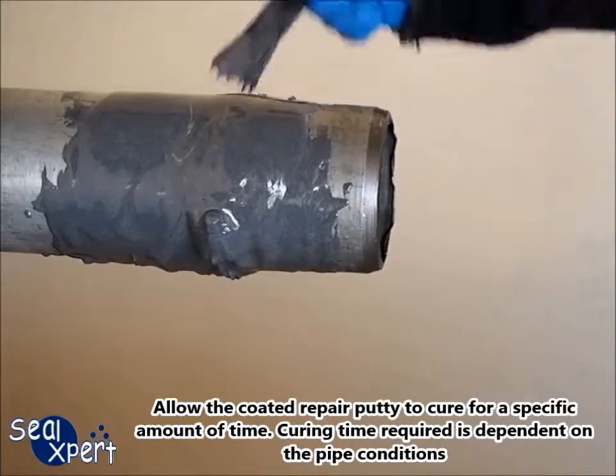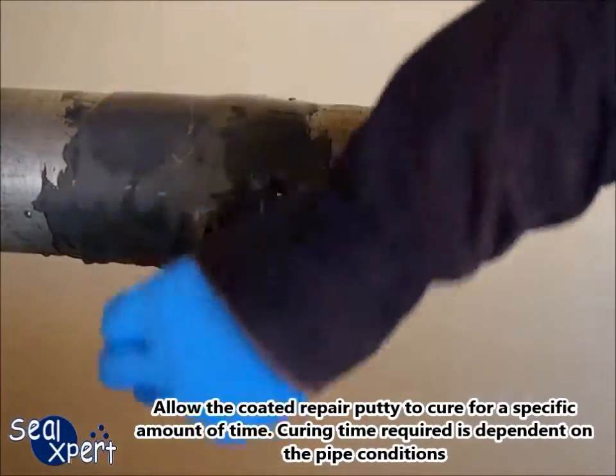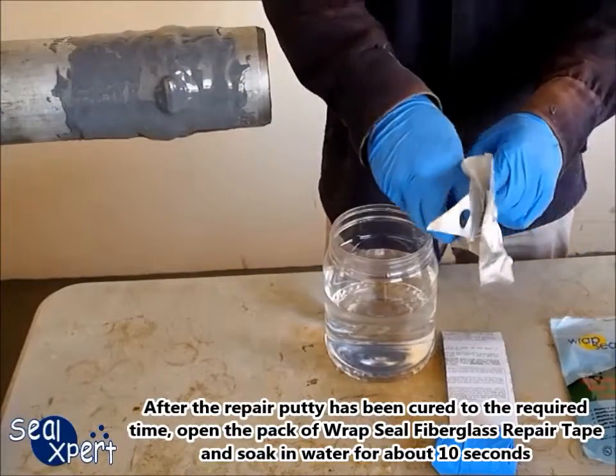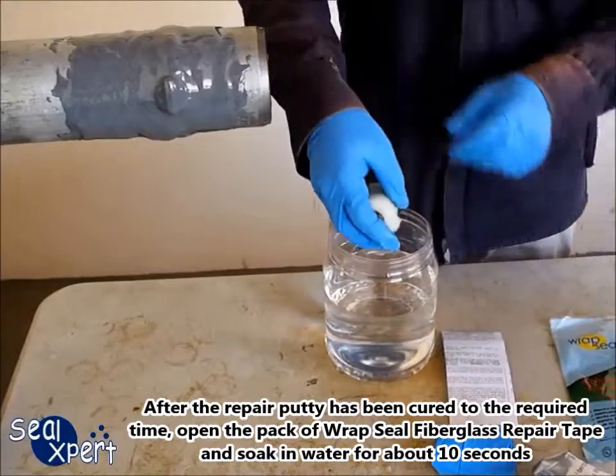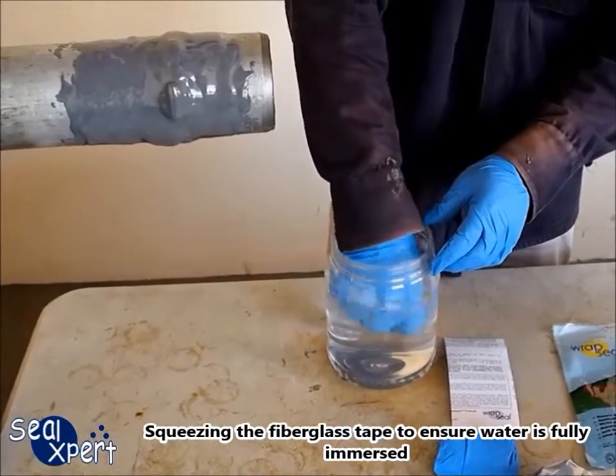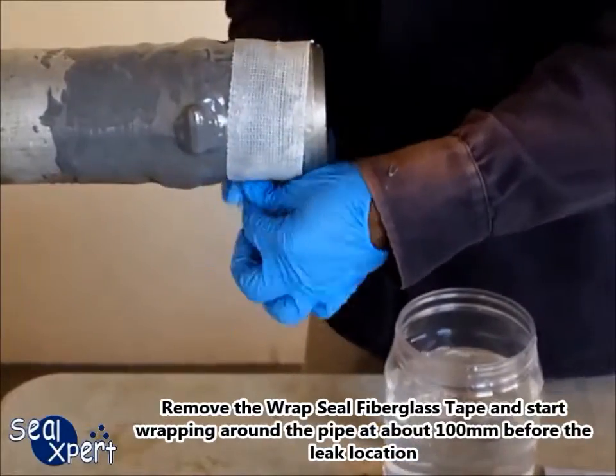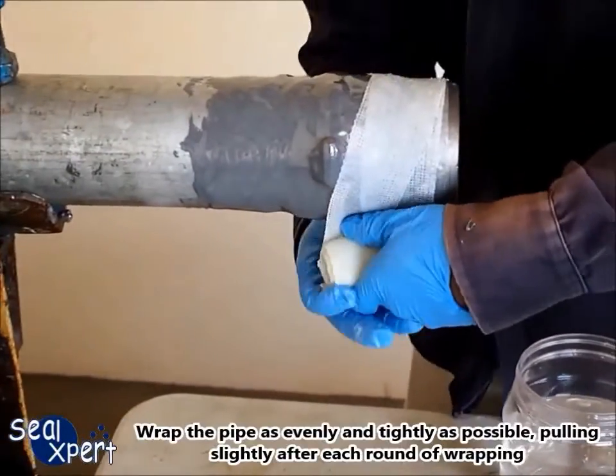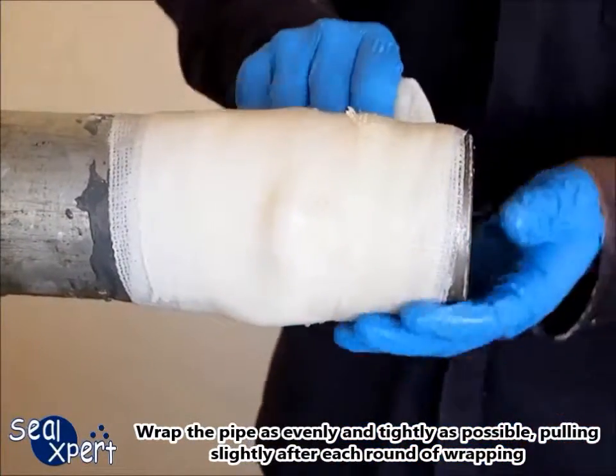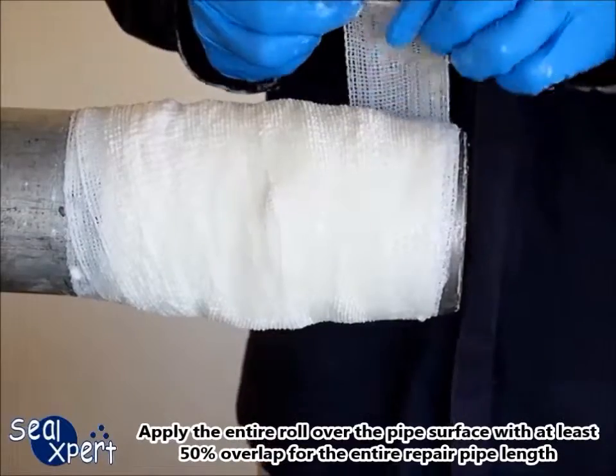Allow the coated repair putty to cure for a specific amount of time. Curing time required is dependent on the pipe conditions. After the repair putty has been cured to the required time, open the pack of Wrap Seal fiberglass repair tape and soak into water for about 10 seconds, squeezing the fiberglass tape to ensure water is fully immersed. Remove the Wrap Seal fiberglass tape and start wrapping around the pipe at about 100 mm before the leak location. Wrap the pipe as evenly and tightly as possible, pulling slightly after each round of wrapping. Apply the entire roll over the pipe surface with at least 50% overlap for the entire repair pipe length.